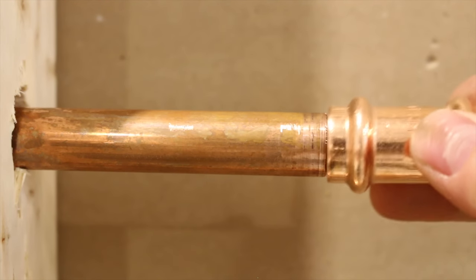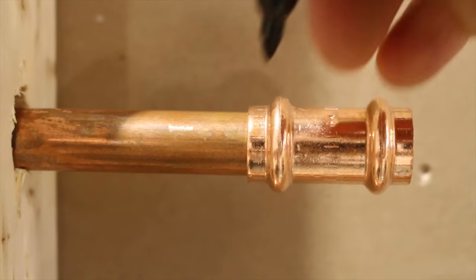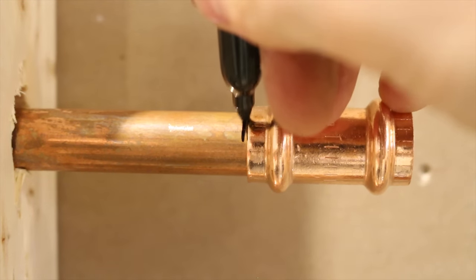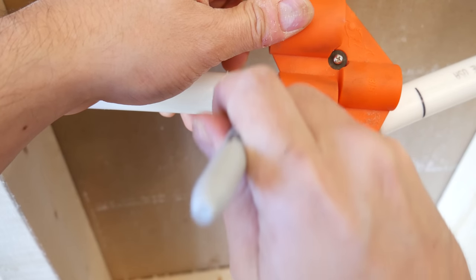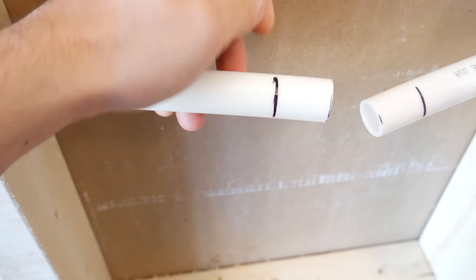For ProPress fittings, insert the fitting fully and mark it before pressing it. And for SharkBite fittings, use a dedicated depth gauge or the depth chart from their website to get it done.